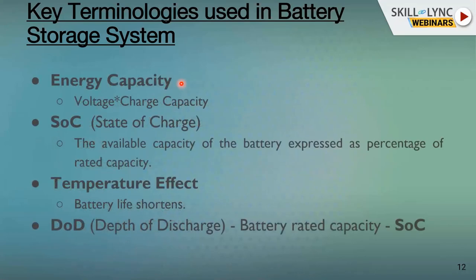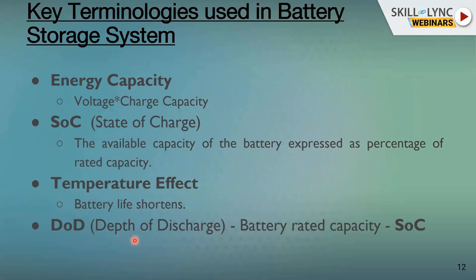Energy capacity is the voltage rating of a battery multiplied by its charge capacity, usually expressed in watt hours or kilowatt hours. State of charge (SOC) is expressed as a percentage of rated capacity — just like your mobile phone displaying 50% or 30% battery, that is the SOC at that instant. Temperature also affects battery life — operation at extreme temperatures, either high or low, degrades battery life. Depth of discharge (DOD) is the complement of SOC; if SOC is 20%, then DOD is 80%.